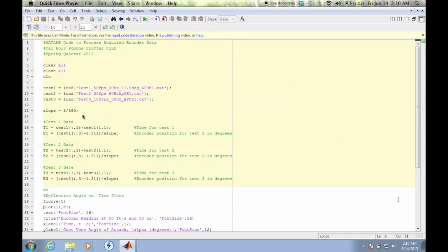One of the changes that was made to the data was to zero out the time. Our data acquisition system encounters a glitch during data logging that causes major discrepancies in time. For example, the time shows 0.5 seconds during the beginning of the data logging, and then it suddenly escalates to 80 seconds. This is the reason that the time must be calibrated to 0.